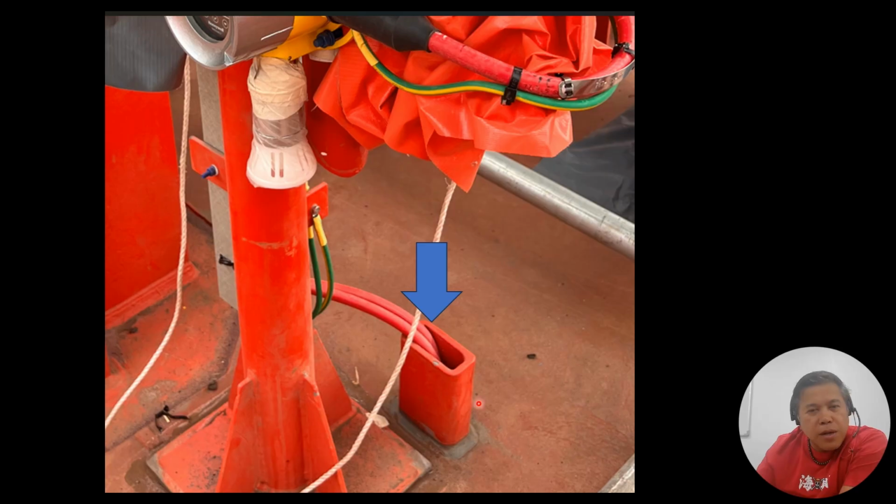This is below deck, then the tray comes below this, and then you are penetrating here, with the cable passing through in this area. As you can see, it's very narrow and small. You can see it's squeezing the cables itself. So this is not the way we accept it as well.